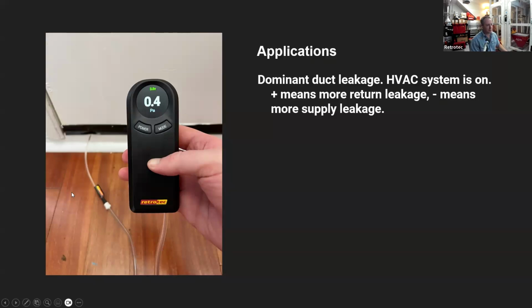So that can kind of tell us about what happens in the house naturally when you're just running fans. Again, too, if you start turning on exhaust fans, bath exhaust, kitchen exhaust, dryers, you can see what happens to that house pressure as you start to kick those fans on, and to see what that infiltration looks like in real time as people are living in the house, to help narrow down where the source of some high humidity complaints might be coming from, comfort complaints, things like that. Being able to read pressures accurately in a small amount can tell you a whole lot about what's going on in a building. So, this manometer and that probe, since it's a rigid metal, you can shut a door over it, is great for that.